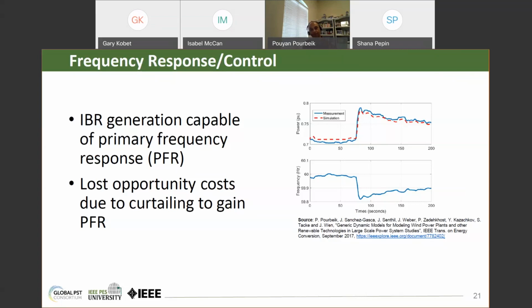The point is, if you want to do this all the time, there is a cost, because there's opportunity cost for keeping a wind or PV plant curtailed all the time. You're losing money and you're losing generation you could be putting on the grid. So to do primary frequency response for under frequency events, there are commercial issues that may have to be taken care of in a market paradigm, and that's outside the scope of what we're discussing here. But from a technical standpoint, it's doable, and there you have it. And if it was a battery, it's of course always doable because the battery has stored energy. Also, over frequency is always doable with wind or PV because you can always decrease power, right? So if we go to the next slide.